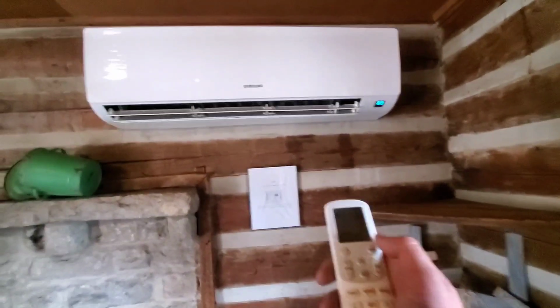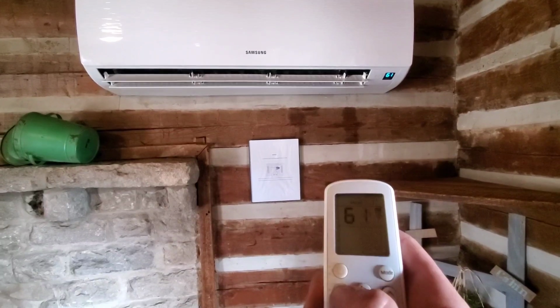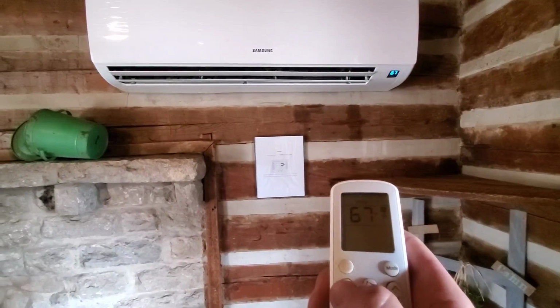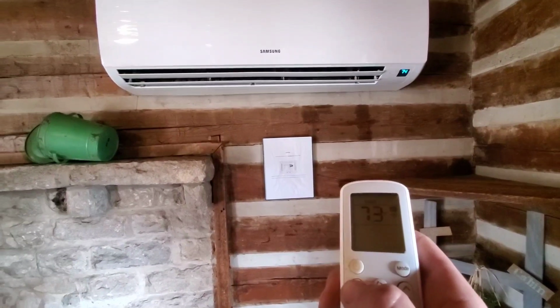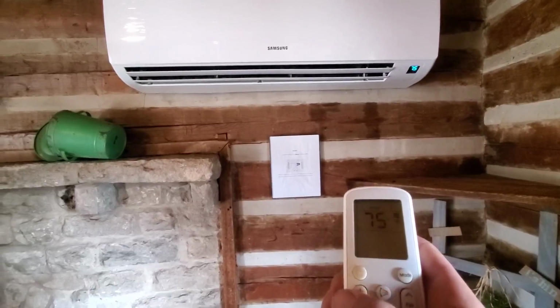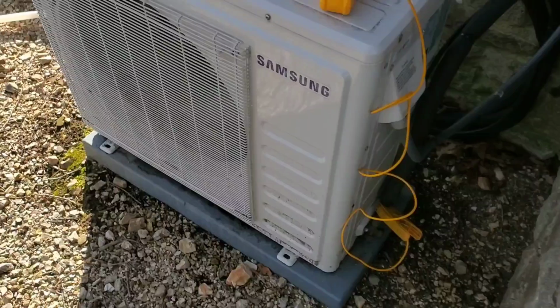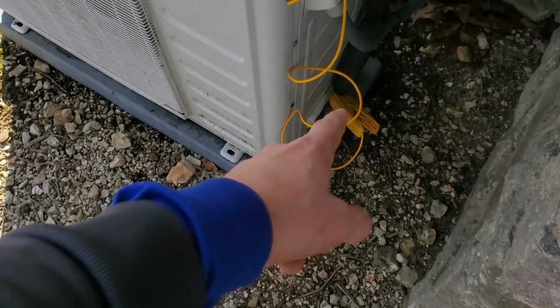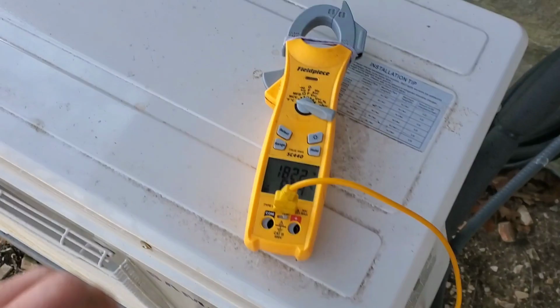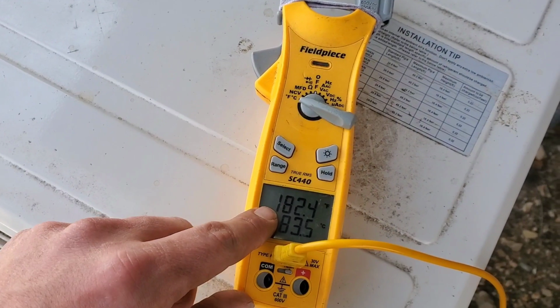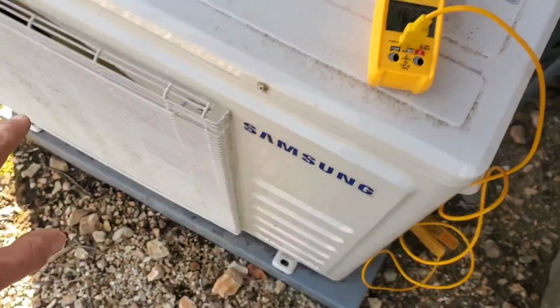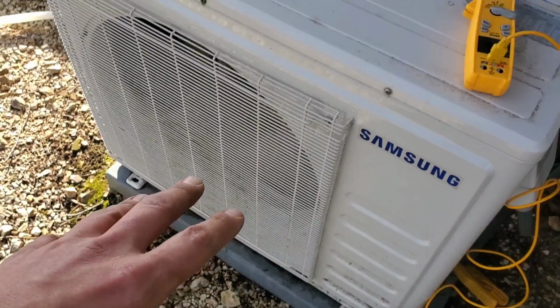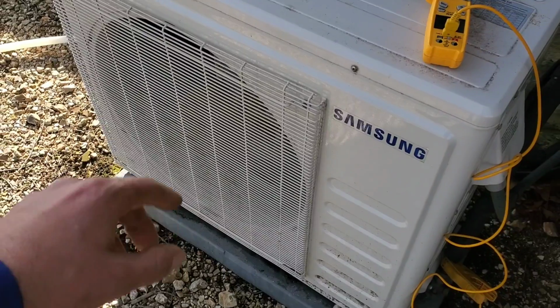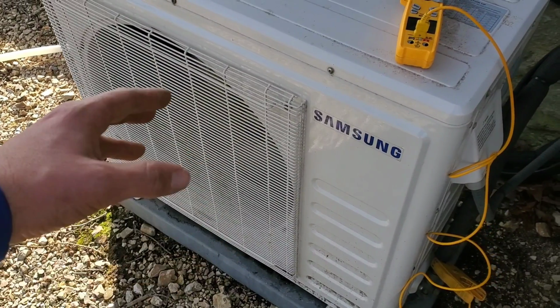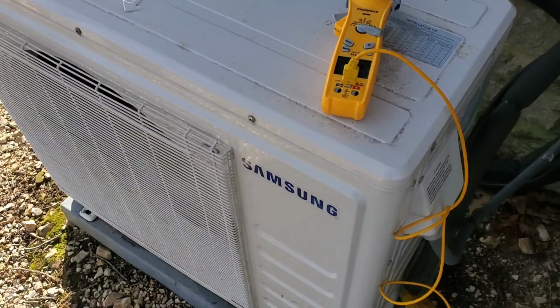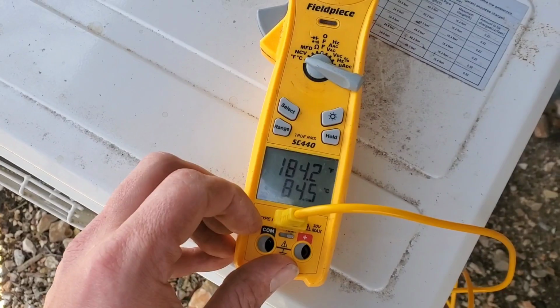Working nicely. Let's turn it to heat. Check the operating temperatures and pressures outside. Let's get on about 74, 75. Good deal. Outdoor unit is running. Temperature probe is on the vapor line. Temperature is 182 degrees. The unit is actually starting to go down in hertz. I think it's changing frequency and trying to reduce capacity because it's probably reaching temperature inside.